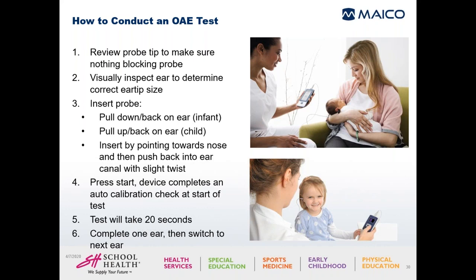Once it's in place, as long as you have a probe tip on the ear, I would not be worried about getting it in too deep, because these are very soft sounds. We want to get that probe in as far as we can, and those ear tips are not going to allow you to get it in too far. So just be aware of that. Once you have the ear tip in place, you're going to be pressing start. The device will go through a calibration check, and then it will continue on with the test. This test takes about 20 seconds. So you complete one ear, and then you just switch over to the other ear and do the same process.